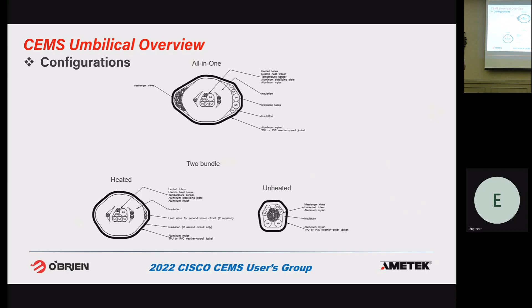Whatever kind of clamp they're using, you don't want to compress the thermal insulation. When you start compressing it, you're defeating the purpose of that insulation, which is to reduce heat loss. Also avoid cable ties or anything with sharp edges which can cut into the jacket.